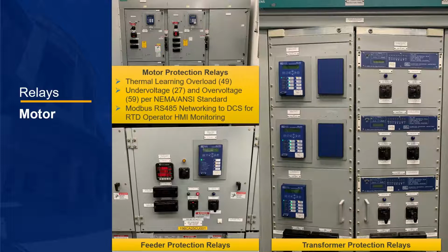Overvoltage settings are set to prevent damage to the motors due to high transient voltages. Motors are typically designed to withstand 75% of their rated nameplate voltage for up to 60 seconds. As such, the undervoltage element, or ANSI 27, is set to trip before this can occur. Other protection functions include the neutral overcurrent, or 50G, mechanical jam, which functions as an instantaneous overcurrent, or 50, load loss/undercurrent, ANSI device code 37, which typically indicates a mechanical failure, and a current imbalance, or 46, which provides protection for winding-to-winding short circuits.